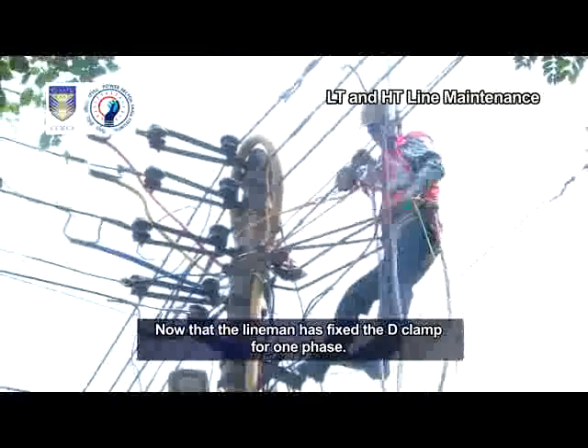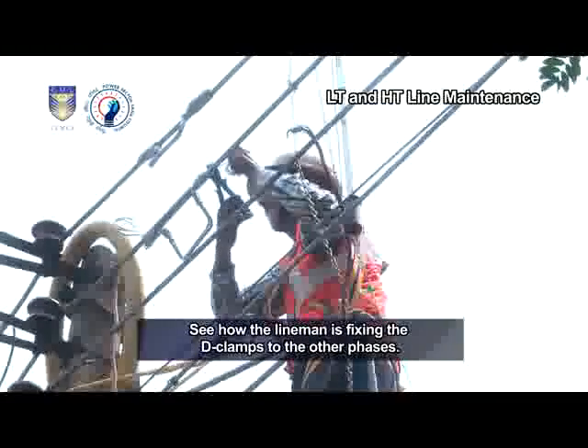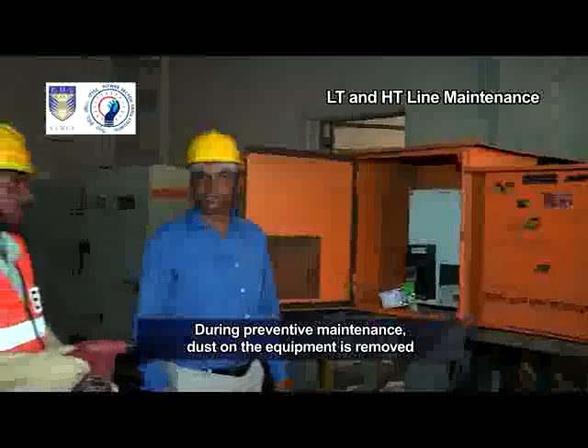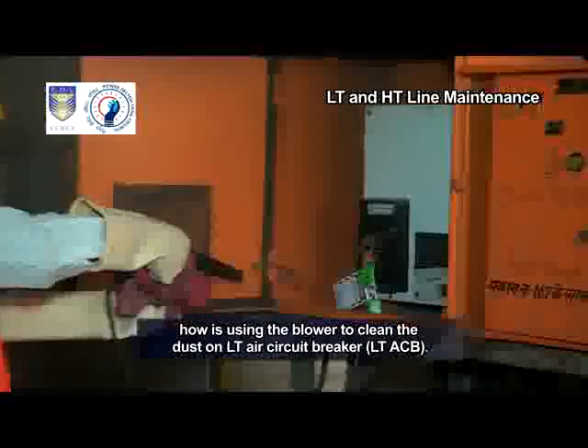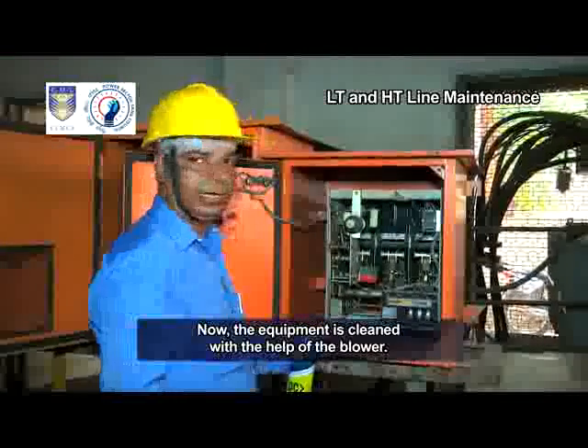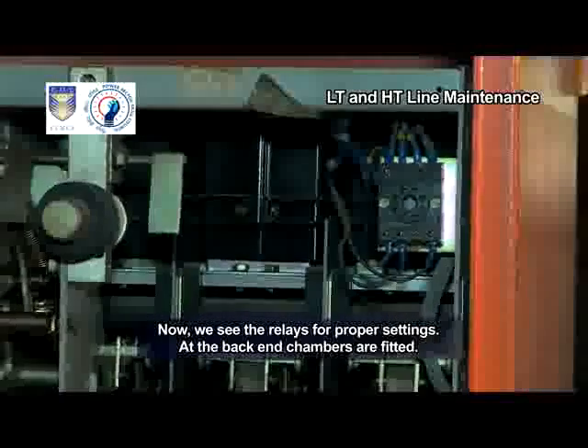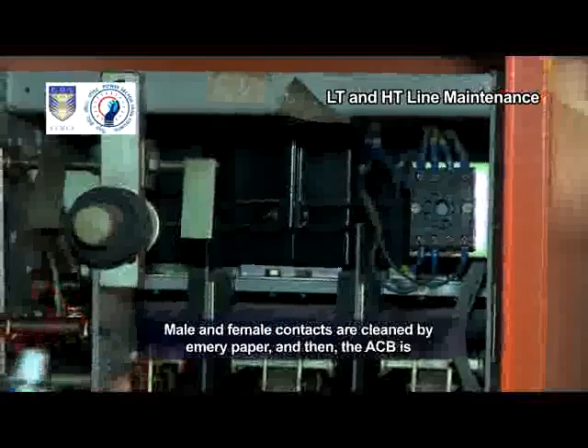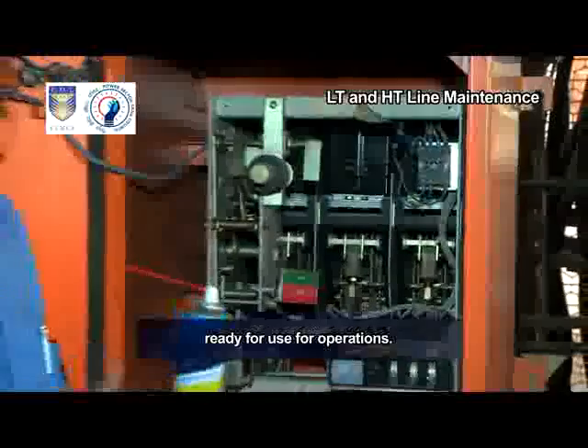See how the lineman is carefully fixing the D-clamp so that there is no loose connection. Now that the lineman has fixed the D-clamp for one phase, he will fix them for the other two phases and the neutral. During preventive maintenance, dust on the equipment is removed with the help of a blower. The lineman is using the blower to clean the dust on the LT air circuit breaker, LT ACB. Now the equipment is cleaned. We see the relays for proper settings at the back-end chambers are fitted; these are cleaned with CRC spray for any carbon layer that may have formed. Male and female contacts are cleaned by emery paper and then the ACB is ready for operation.